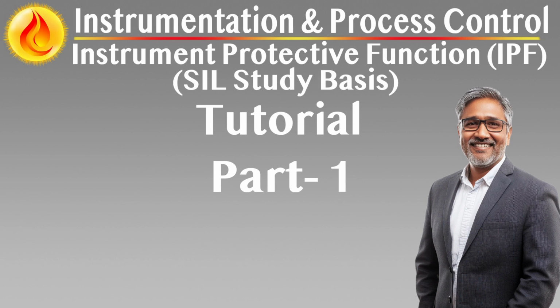Integration with operations and maintenance. IPF classification influences more than just design. It shapes how the function is maintained, bypassed, and overridden in day-to-day operations. Higher classified IPFs demand stricter bypass authorization and logging procedures, alarm prioritization and enunciation differentiation, operator training specific to IPF behavior and response, rapid repair or compensatory measures upon failure.